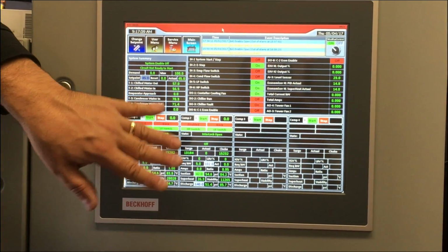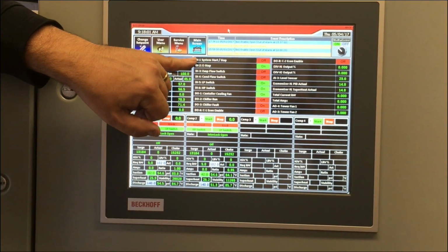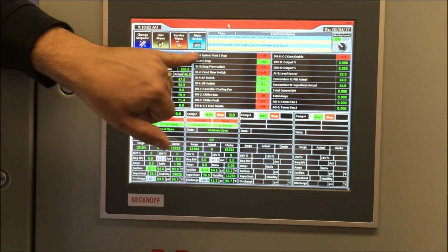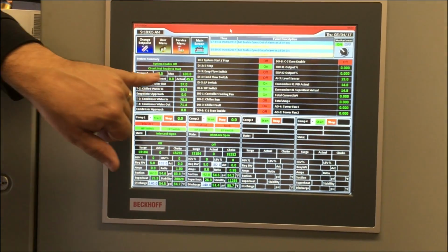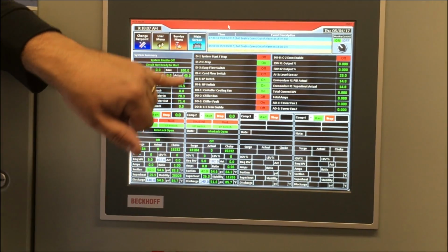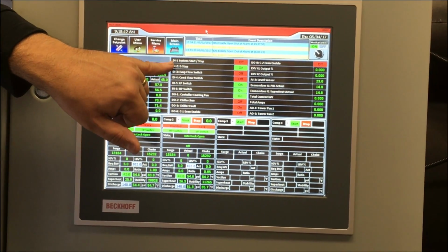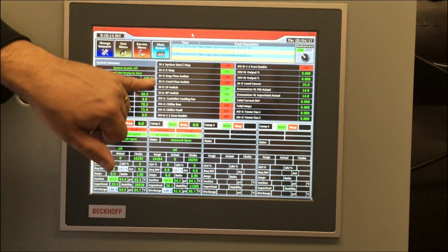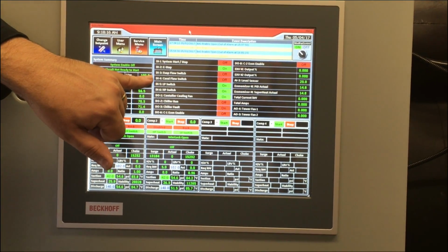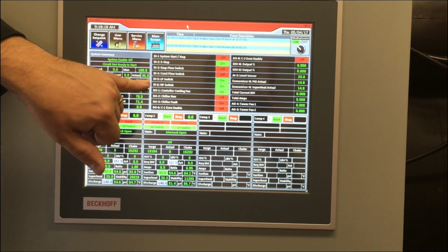So everything here is in nice plain English. So our system start stop is your automation. So if that says off, we're not going to run. Emergency stop, I believe you guys have glass break here, so it's wired through the glass break, so that's on, which is a good thing. Flow switches, on and off, condenser and evap. High pressure, low pressure switch.